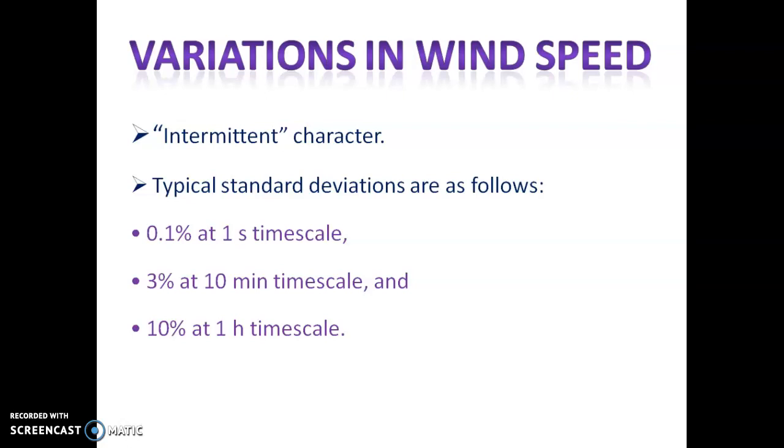The measurements showed very little energy in the region between 10 minutes and 2 hours. This region we call the spectral gap. The output power from a wind park, having 6 to 10 turbines, follows the Kolmogorov spectrum.